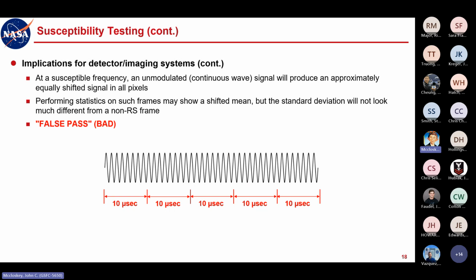I mean, it was a test in the lab. If it was a full-up official test in the EMI lab, we would have applied the modulation, right? But this was just a diagnostic test in a lab. And it appeared that we were not seeing any interference when everything told us that we should. We should definitely be seeing some interference from this applied signal.